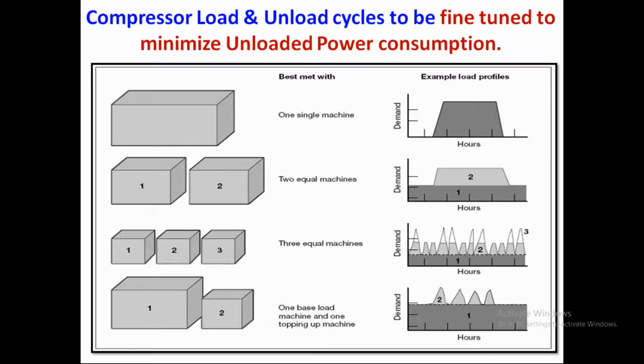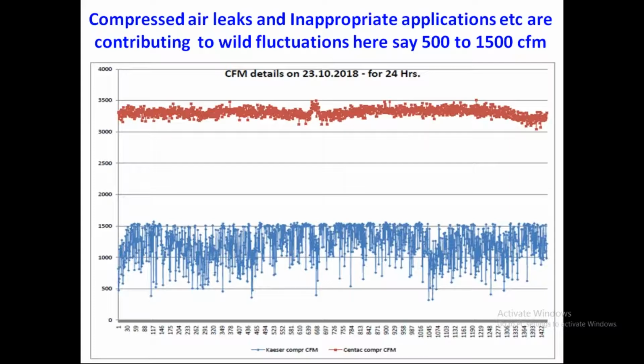Instead of that, have a base load and go for a VFD, and that VFD will modulate the second compressor, the standby compressor, to maintain the cleaning flow as well as the pressure. But you need a cleaning receiver for this. You can see this industry is running almost 3500 CFM consumption, out of which the second compressor, because of cleaning and leakage, not only cleaning, because of leakage, sees a drop or fluctuation of 500 to 1500 CFM. That leakage definitely has to be arrested.